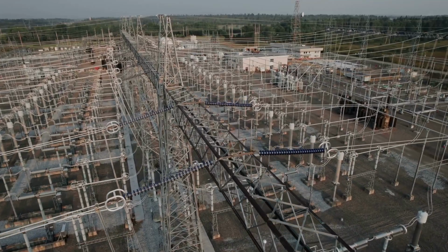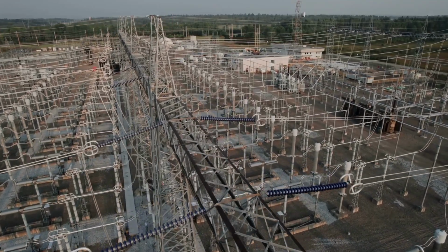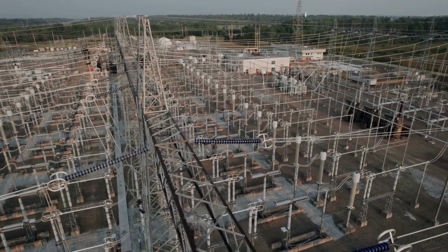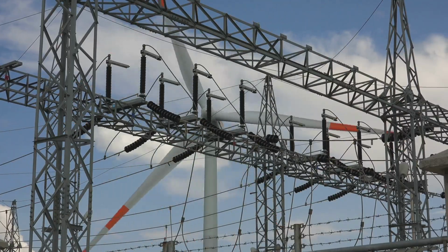Volt-VAR mode. The DER modulates reactive power output in response to terminal voltage changes. This is one of the most important modes for fault ride-through because it enables real-time voltage support during grid disturbances. Watt-VAR mode. Reactive output changes based on active power, useful during partial loading or curtailment.